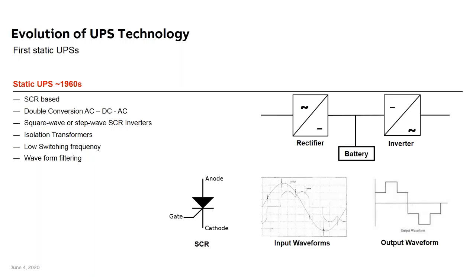Functionality is the same as we just talked about. The single line, that's what it looked like back then, still today. The drawback with the SCRs is that we can gate them on, but we need a zero crossing off, we need to do forced commutation to switch them off. So it's a very solid, rugged device. But the harmonics was a big issue with early generation UPSs.